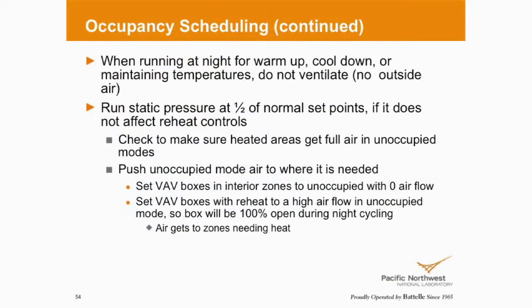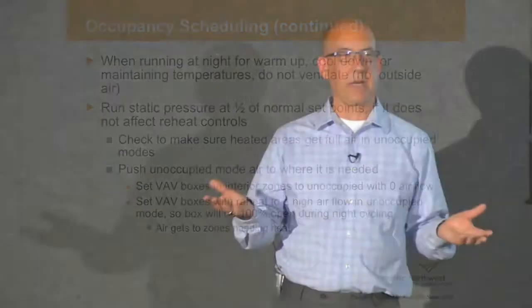If I'm running at night, and when I say night, so we've got a schedule on a fan. Normally, and I've seen this, how many of you have BAS systems? If you go into night setback, does it have a low limit and an upper limit that will let the space either cool down to or warm up to? Hopefully everybody has that, right? Because a lot of BAS systems are configured and the control vendor doesn't put that. The capability is there, he just didn't program it in.